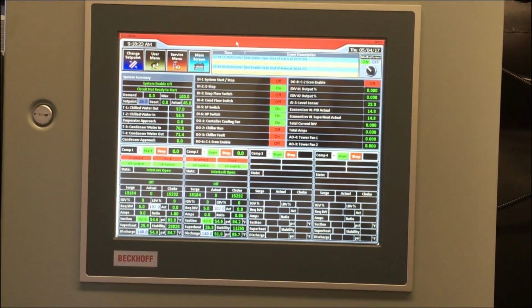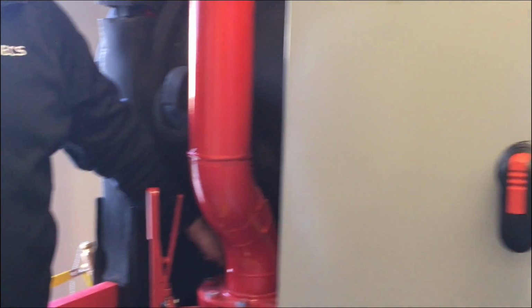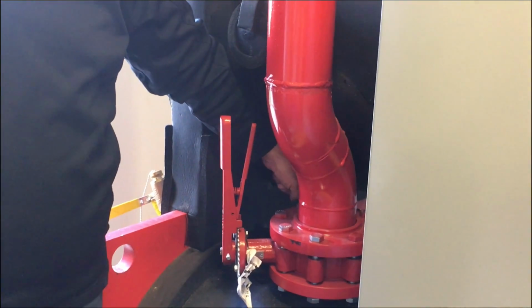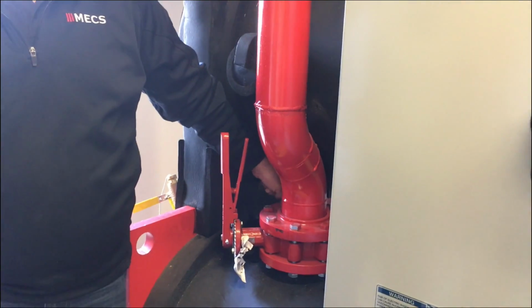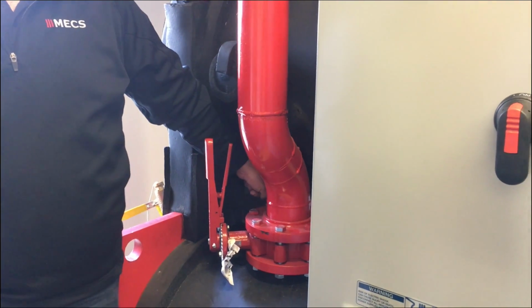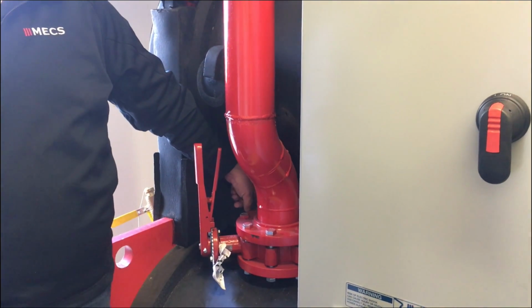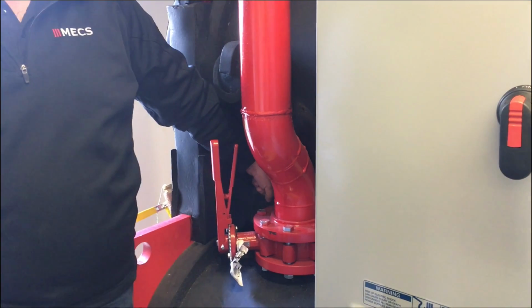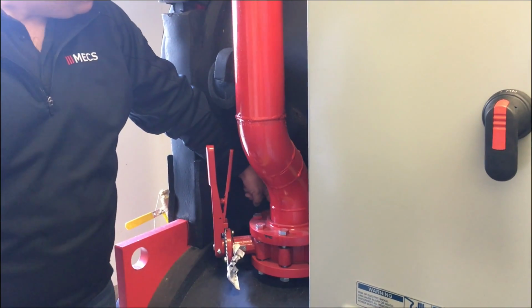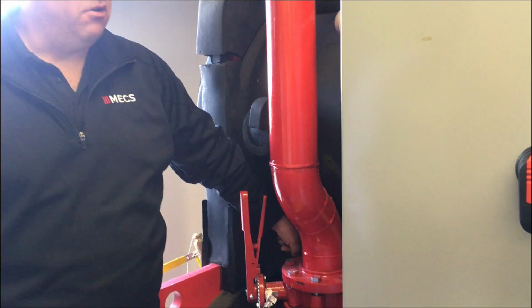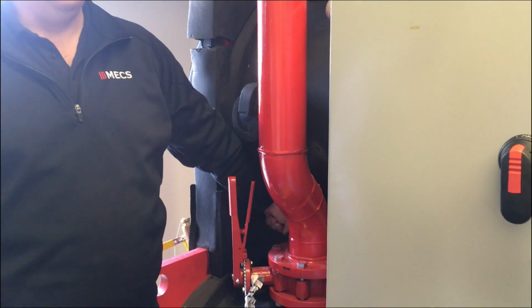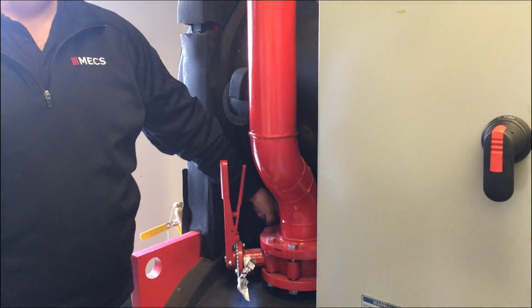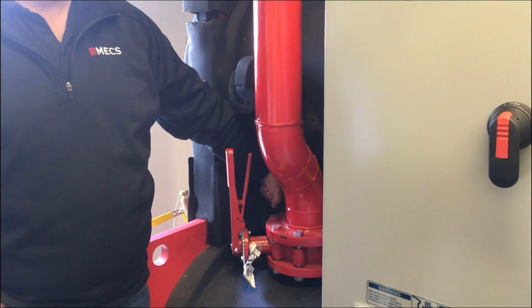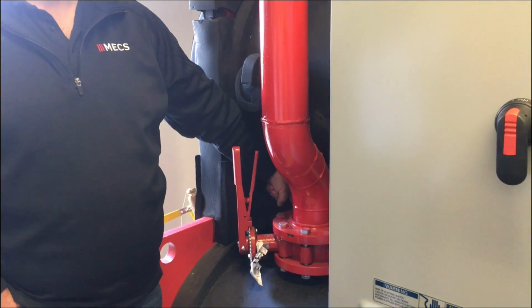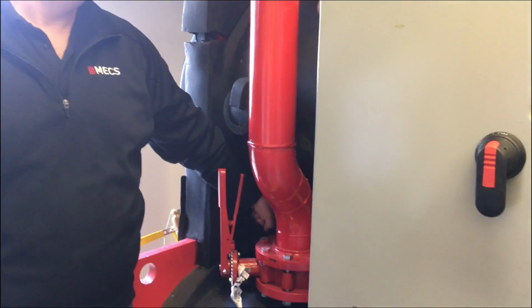There's one high pressure, one low pressure switch on the entire machine. The high pressure switch is right here on the pipe behind here, and it's got a manual reset button on it. This is your third stage of high pressure safety. So if this trips, something's happened quickly, like your tower, literally the fan belt broke, or something happened and we're not moving. But the first two stages are electronic, which are always slower than the button, but they're set lower. I think it's 185 for the chiller's high pressure cutout. It's 205 for the electronic high pressure cutout, and this one's 215.